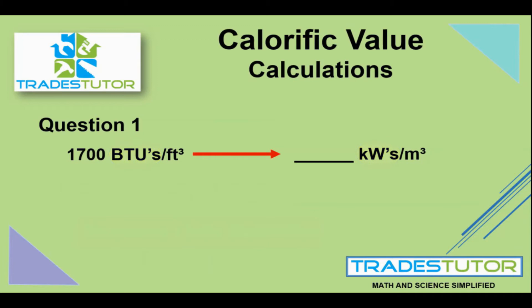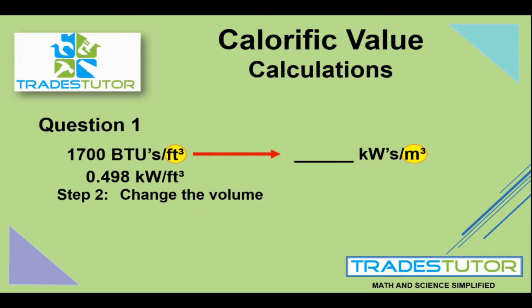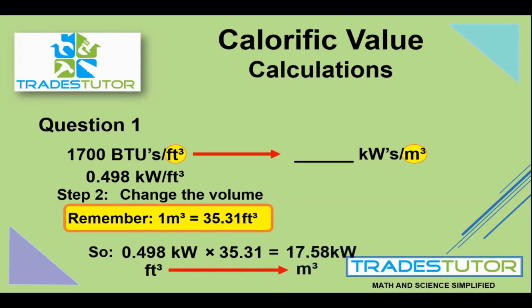So we put the 0.498 over here and realize that's still per cubic foot — we still have to change the volume. We're going from a cubic foot up to a cubic meter, which is a lot bigger, so there's going to be a lot more gas in there. One cubic meter is 35.31 times bigger than a cubic foot. So we multiply 0.498 by 35.31 to get 17.58 kilowatts per cubic meter — another way to express the calorific value of the gas, equivalent to 1,700 BTUs per cubic foot.